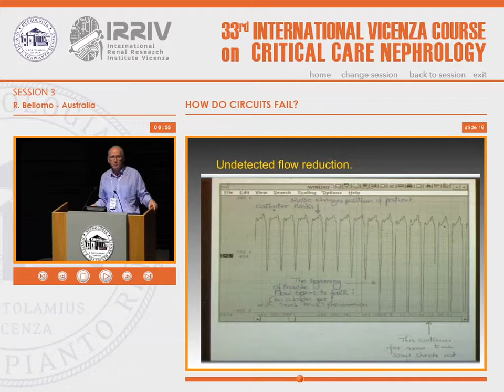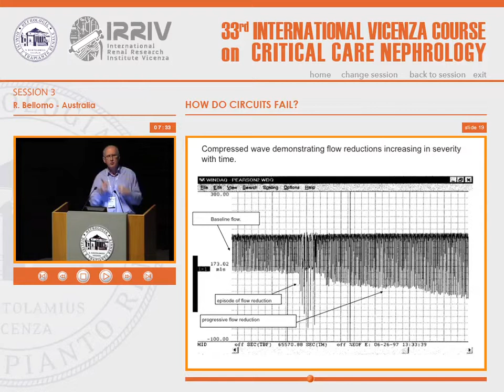you have periods where the blood flow almost disappears. And you can squash it and show it over a significant period of time, and you can see that you have systems and situations where the machine does not actually know, you don't actually know, the nurse doesn't actually know, the patient doesn't actually know, but the actual flow, despite the rotations of the pump, is dissociated from the pump rotation. And of course, if the flow is less and the ultrafiltration is the same, the filtration fraction goes up, the membrane gets caked up with layers of platelets and red cells and proteins which are being sucked very hard during effluent creation, and over a period of time you're going to lose the filter.